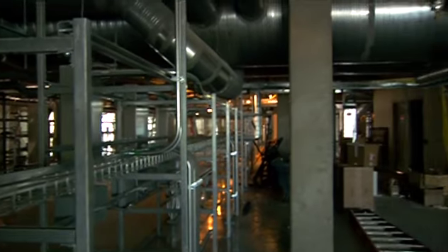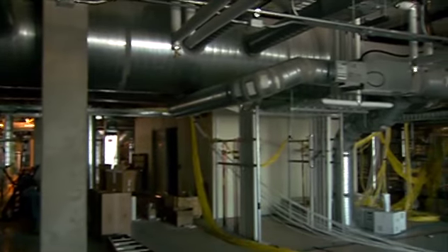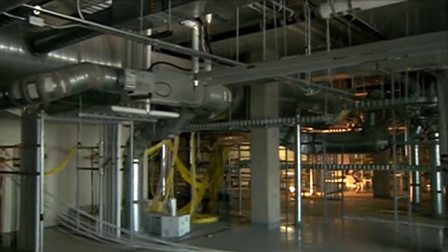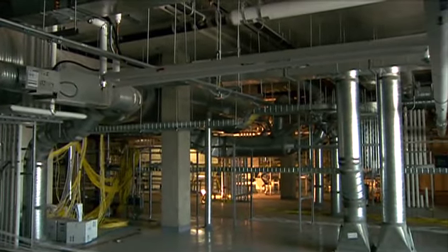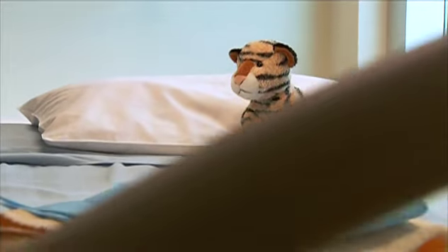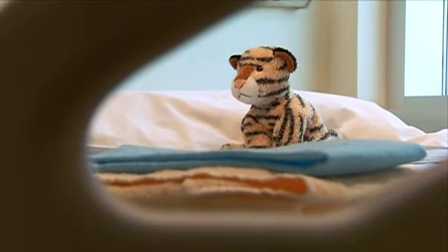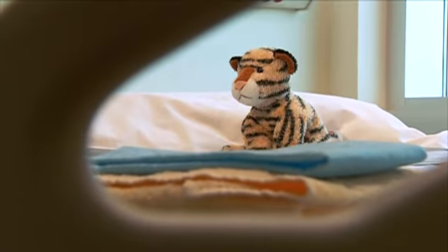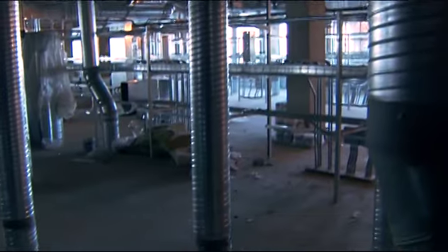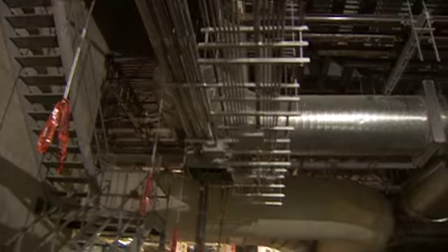Normally, all that equipment gets housed in the ceiling space of the room. What that means is that if there is some maintenance that has to occur, they basically have to shut down an exam room or an X-ray room to do that work. By having it in the interstitial floors, we can get our maintenance people up there to do the work without affecting the room below, so there is no room downtime.